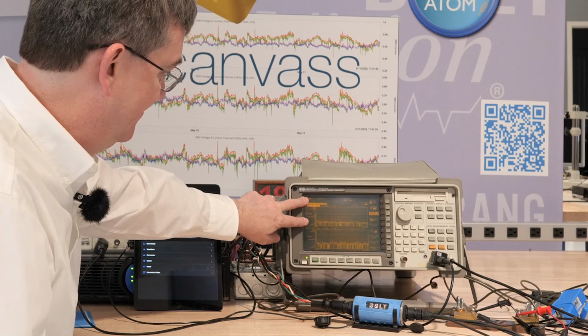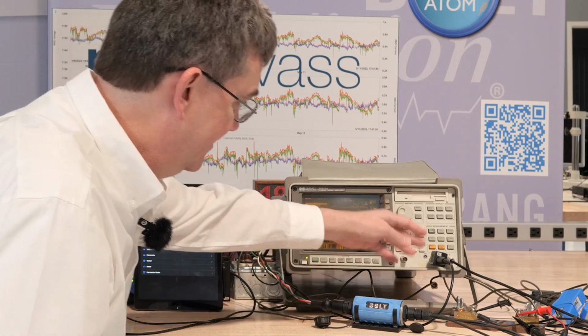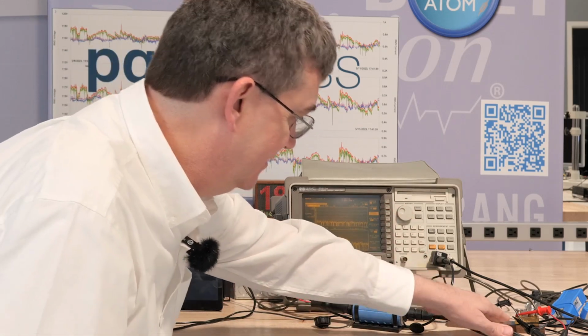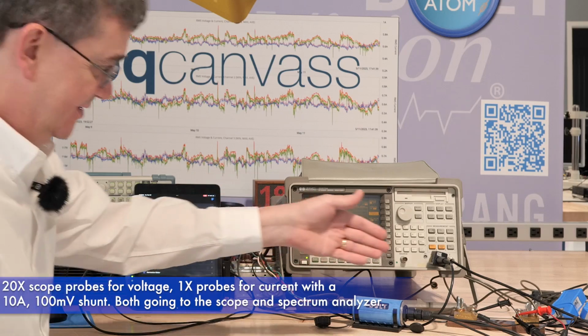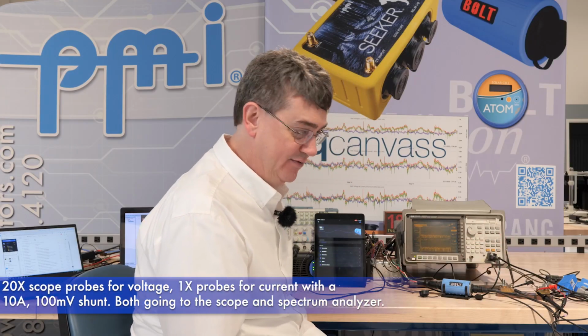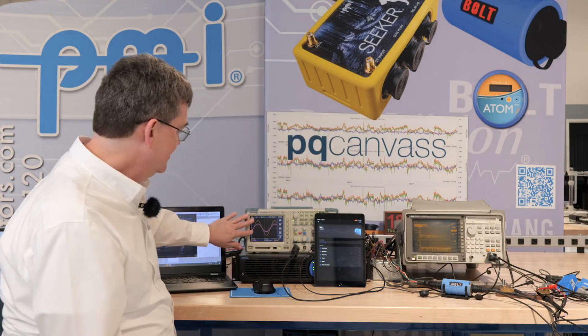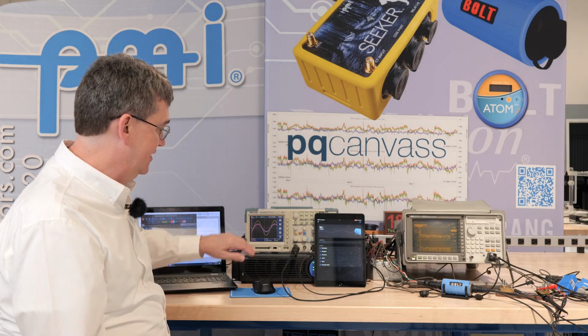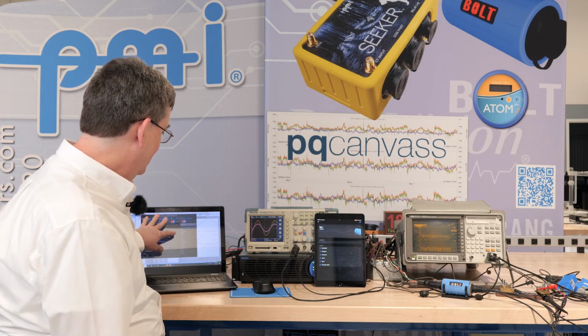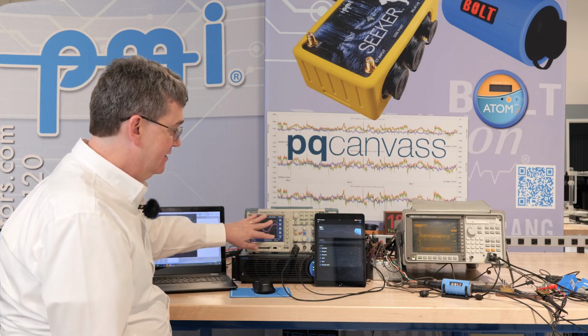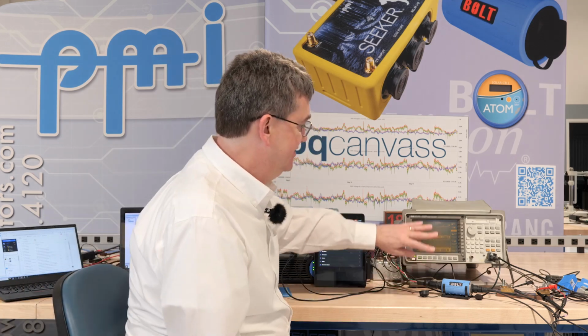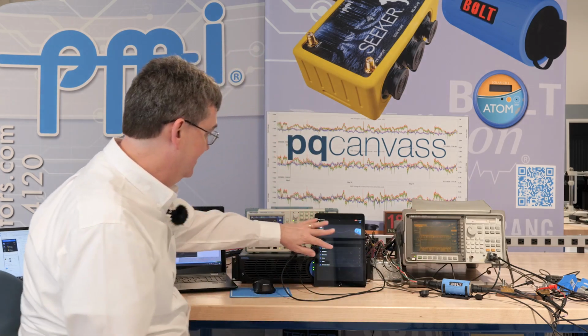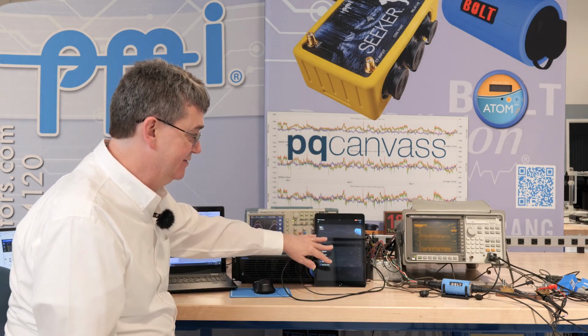We have voltage on the top plot, current on the bottom plot, with a 20-to-1 probe for voltage, and we're measuring on a shunt that is designed for 10 amps full scale with 100 millivolt output at that current, and also looking at the voltage and current waveforms here on the scope, so we can make sure that we're generating what we think it generates, and make sure the bolt agrees with the spectrum analyzer. And we're using the PMIView app on an iPad connected to Wi-Fi.